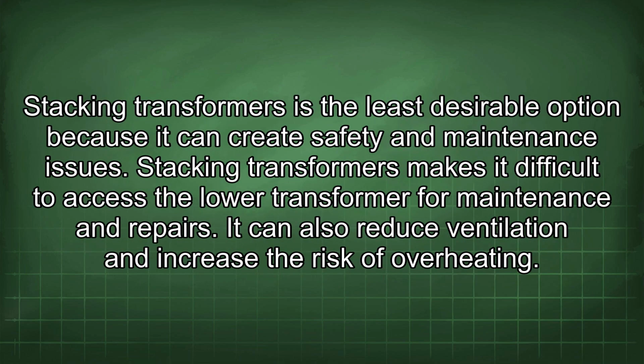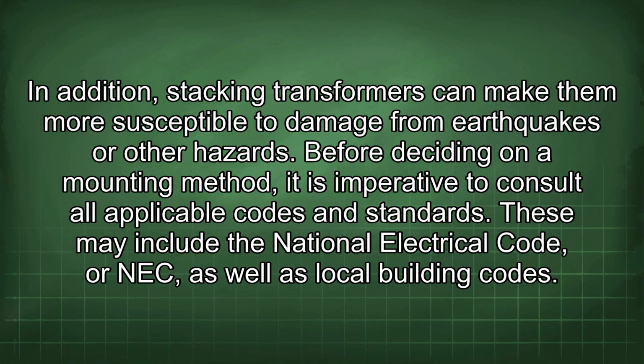Stacking transformers is the least desirable option because it can create safety and maintenance issues. Stacking transformers makes it difficult to access the lower transformer for maintenance and repairs. It can also reduce ventilation and increase the risk of overheating. In addition, stacking transformers can make them more susceptible to damage from earthquakes or other hazards.